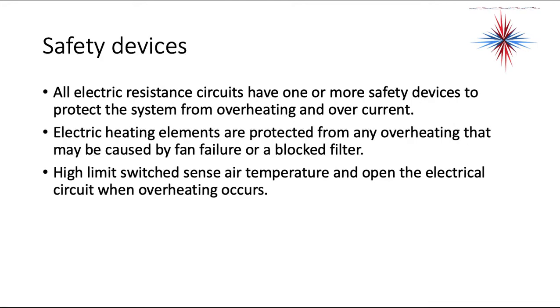All electric circuits have one or more safety devices to protect the system from overheating and overcurrent. Electric heating elements are protected from overheating that may be caused by a fan failure or a blocked filter. The high limit switches sense air temperature and open the electrical circuit when overheating occurs.